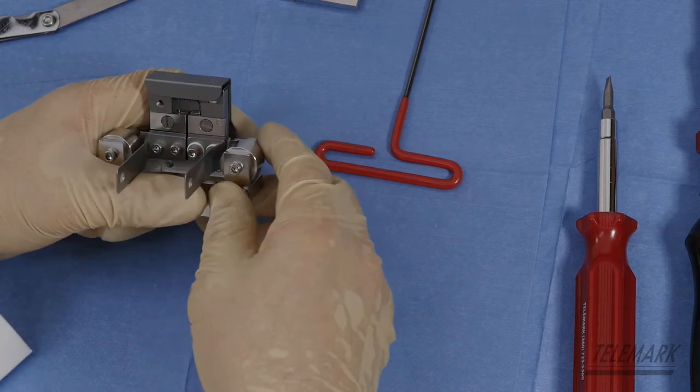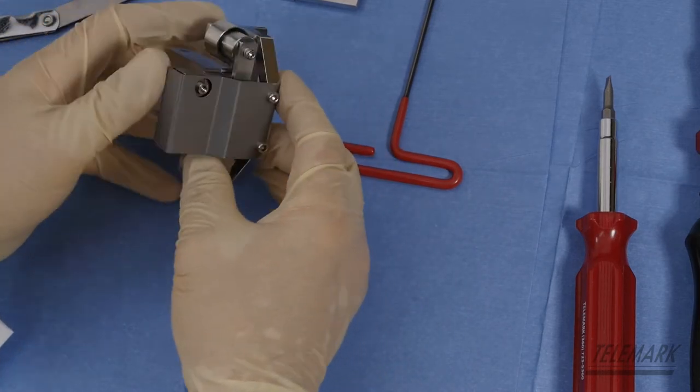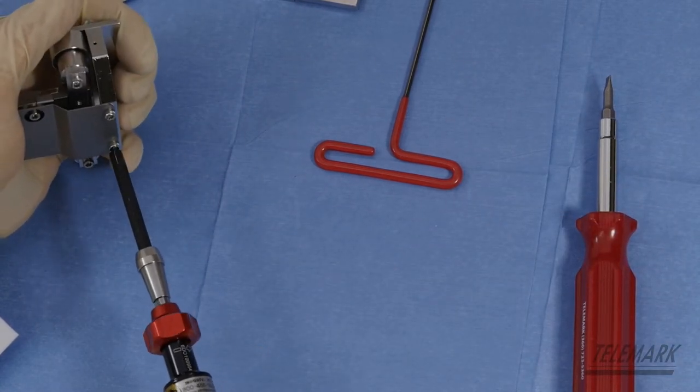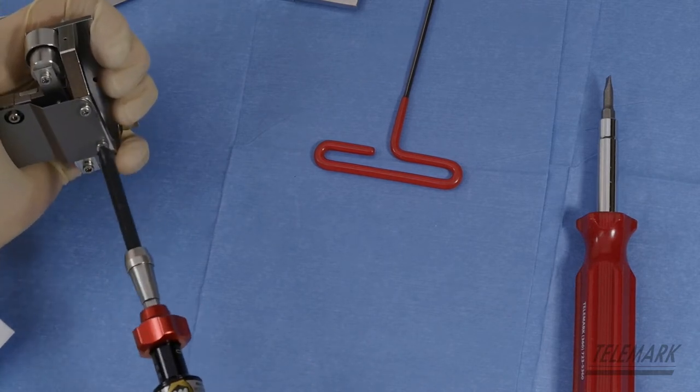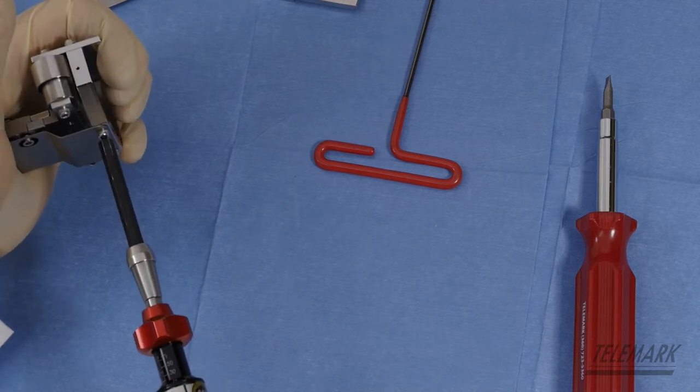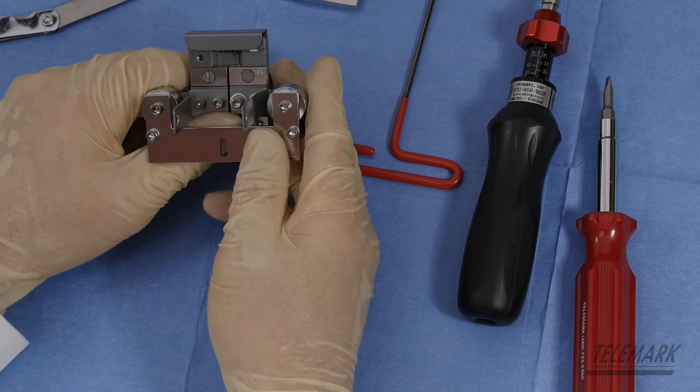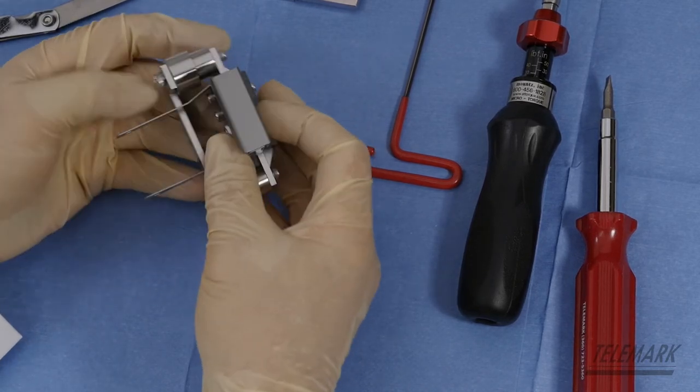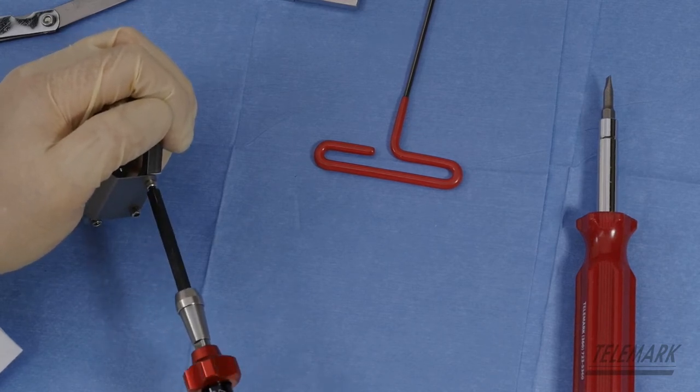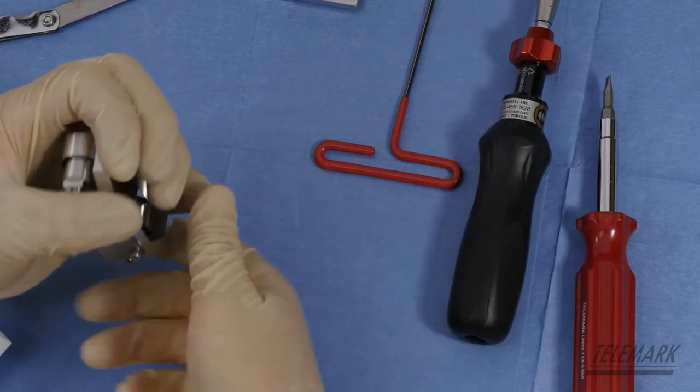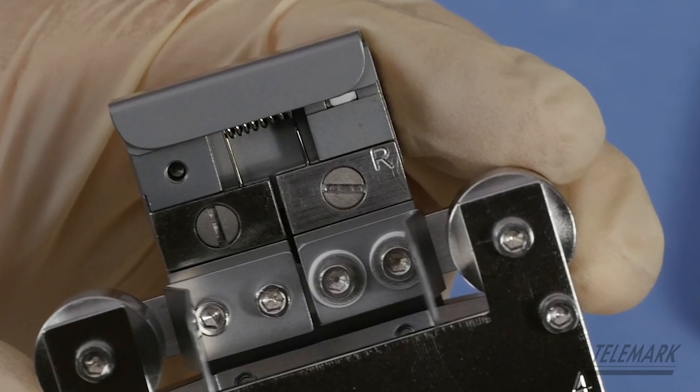In this case we're probably going to have to do some adjusting because the beam former is down a little low and it's not really parallel across. We'll have to loosen that. Push down on the top of the anode in this little hole, using the play in the screw holes on the anode to adjust it. Make sure it's nice and snug and tighten it down. That should be relatively serviceable. Let me try this one more time. There we go. That should get you a serviceable emitter. Your beam former and anode are pretty much parallel with one another.